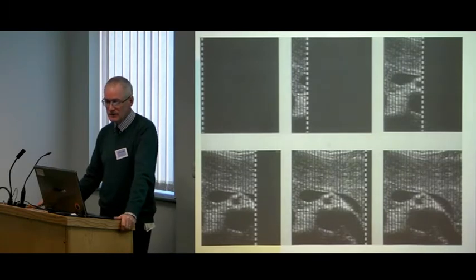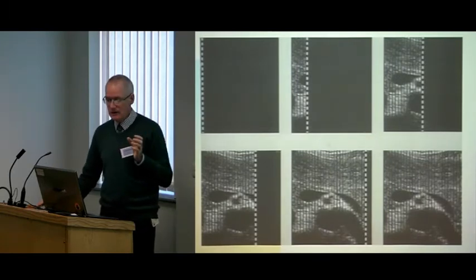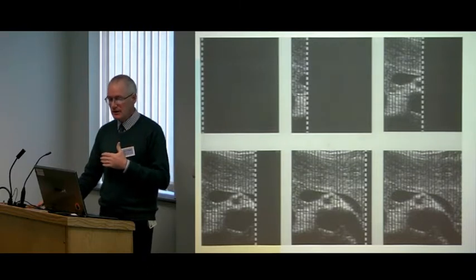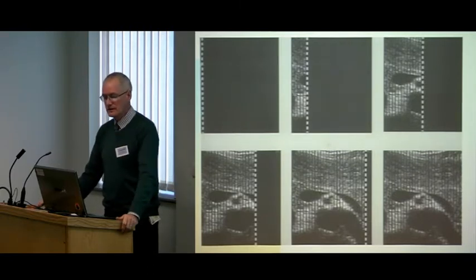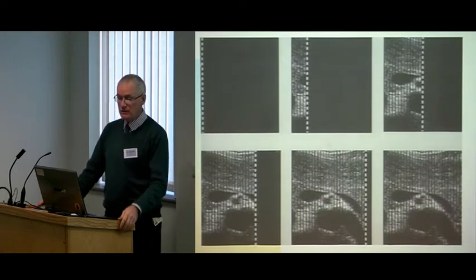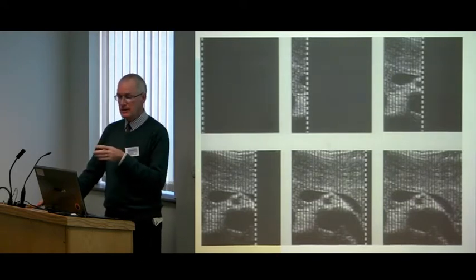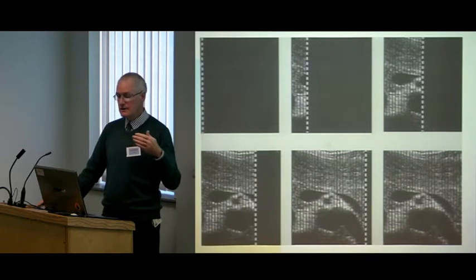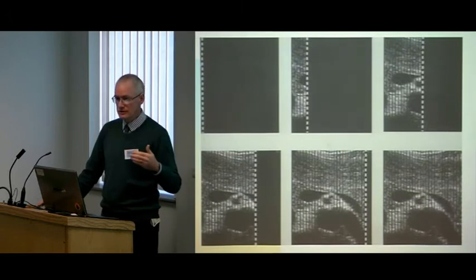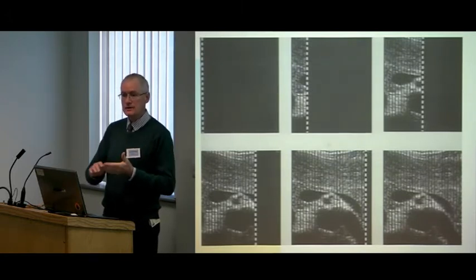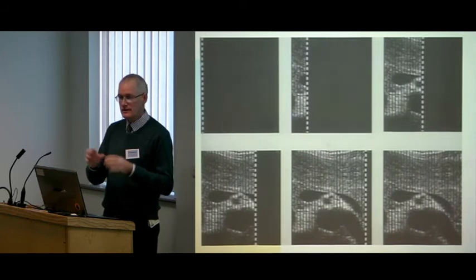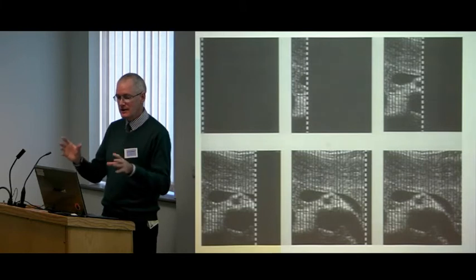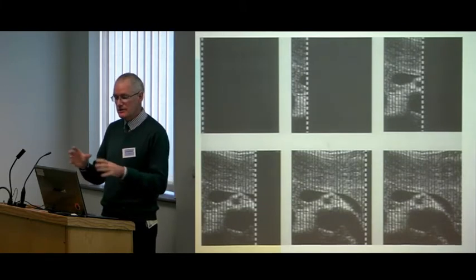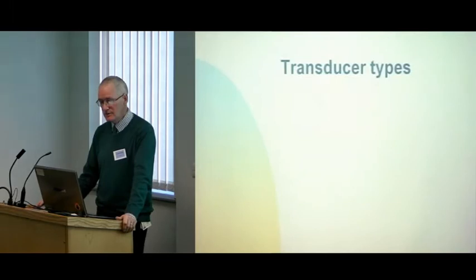So refreshing the frame rate on the actual screen is an important thing to consider when you're actually moving the probe around the patient. If you have too many functions on, the machine will take so much time to plot the image that it will be relatively juddery. So multiple functions and moving the probe sometimes results in a juddery image on the screen. So that's another thing to consider apart from your choice of probe, your depth, your frequency, your amplification, your gain. It's starting now to build in your head. It's starting to get complicated now. But those are the basic things that you have to have in the front of your mind when you're actually using the machine.